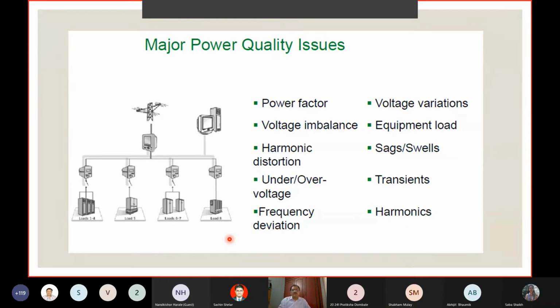Informations. So when we come to some standards on power quality particularly, up to now you have seen some sharing of some practical studies. Now let us take a look at the power quality issues. See, most of the power quality issues in factories are classified very simply as power factor, voltage variations, voltage imbalance, equipment loads, harmonic distortion, sags and swells, under or over voltage, transients, frequency deviations, and harmonics. So each of these topics has in some way or other impacts on the performance of the equipment and also on the energy. So you have to give adequate importance to these topics. The more you learn, the more you apply, the more you practice, you will be able to quickly arrive at what is the problem facing the industry or the equipment.